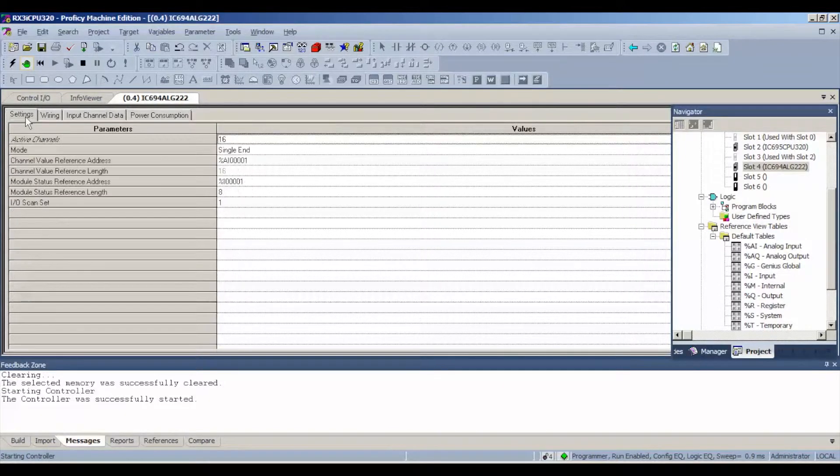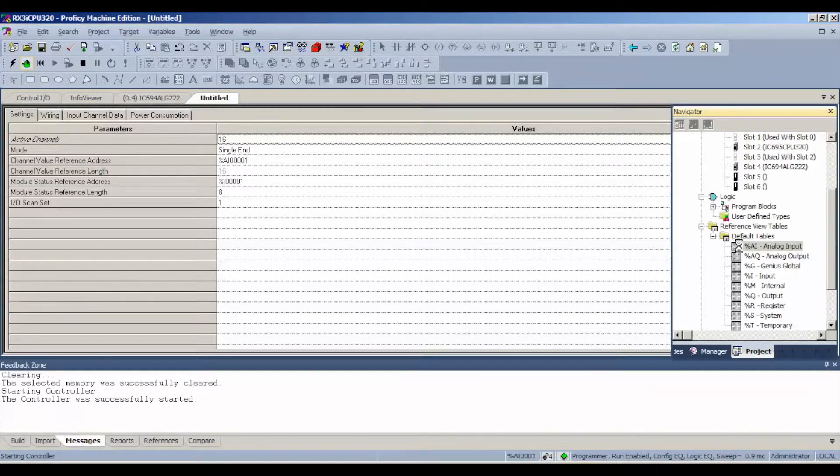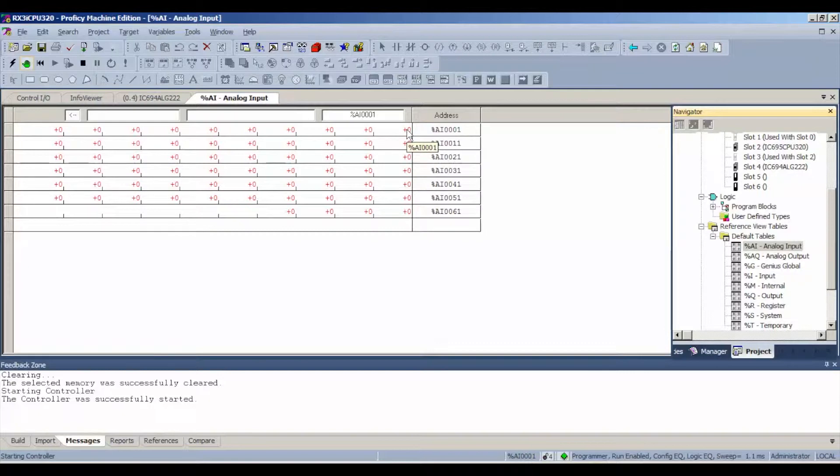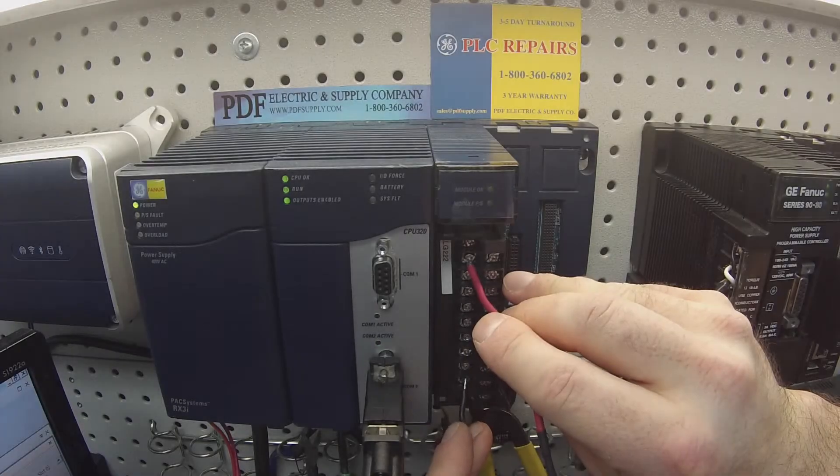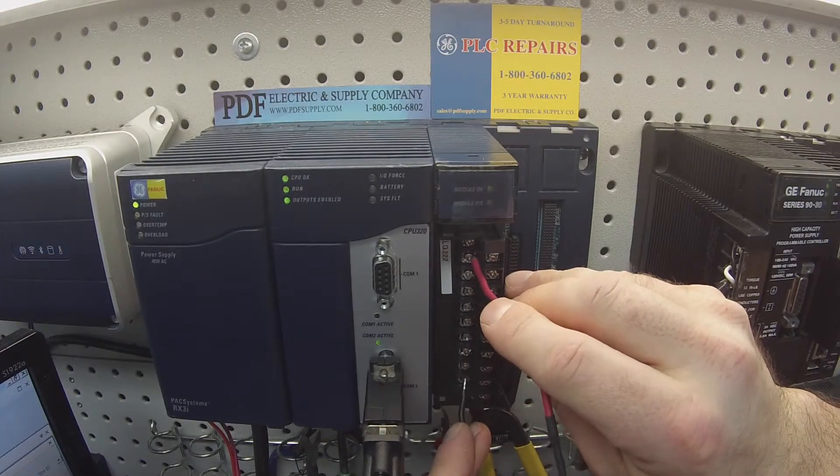If you look at your settings, our reference address, our first channel's going to be on 00001 analog input table. Here's our address. You can see my arrow hovering over it, and it's giving me an illumination that says analog input 00001. According to the wiring diagram, I'm going to plant my negative lead on terminal number 19. That's the bottom left-hand side. To activate channel number one, I'm going to put my positive lead on terminal number three.